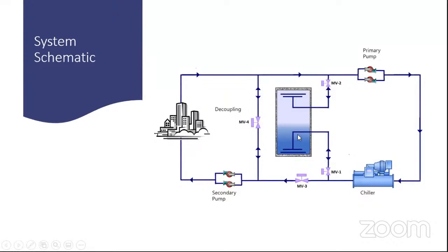You see, there is no pump here. Unlike in the ice case, where there was a separate TES pump, a thermal energy storage pump, here there is no separate pump. With the suction pressure in this line, the water is drawn, and whatever the load is, it is entirely taken care of. So that's my answer.